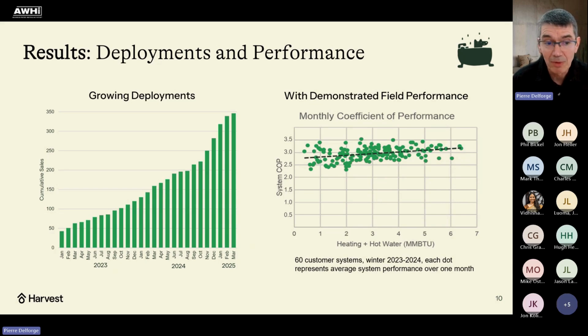In summer, for example, we only charge maybe 30% of the tank—just enough for domestic hot water use. Because it's completely stratified, we can charge the top third or top quarter of the tank, or whatever is needed for that particular home to meet their hot water needs, plus a margin. That minimizes thermal losses over time and allows us to have this level of high efficiency and low thermal losses.